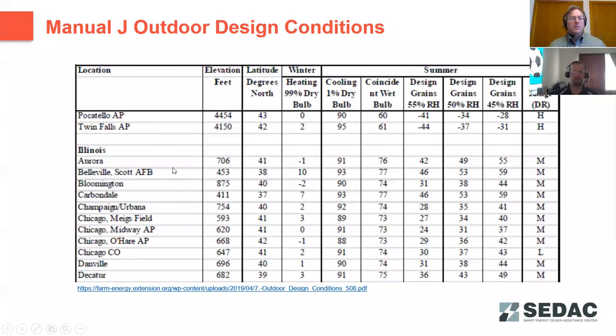Another thing we'd like to call out for Manual J outdoor load calculations: ASHRAE produces these design temperature charts. They are included in the Manual J. They're also included in the ASHRAE Fundamentals books, and I think in the front of the IECC as far as design temperatures for the different climate zones and regions. But we would like to call out that none of these have a design temperature of 100 degrees. If you get a Manual J that has that as a design temperature, send it back, it's not correct.